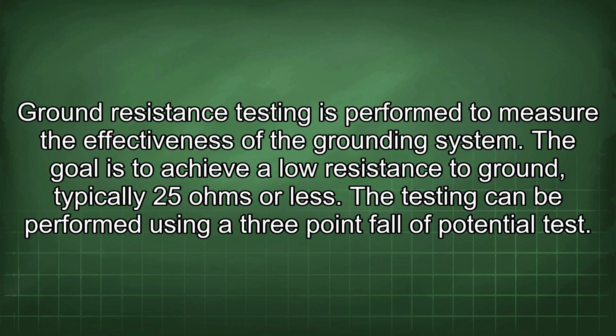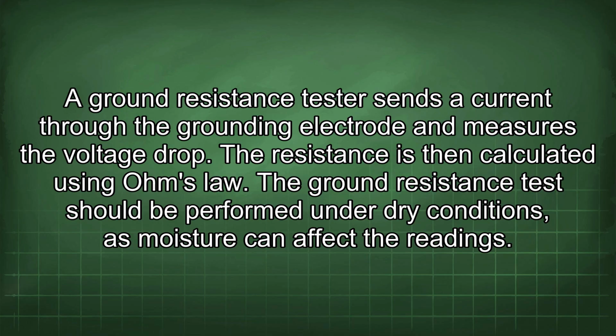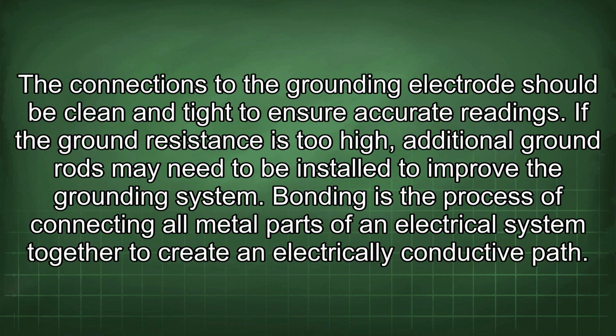The goal is to achieve a low resistance to ground, typically 25 ohms or less. The testing can be performed using a 3-point fall of potential test. A ground resistance tester sends a current through the grounding electrode and measures the voltage drop. The resistance is then calculated using Ohm's law. The ground resistance test should be performed under dry conditions as moisture can affect the readings. The connections to the grounding electrode should be clean and tight to ensure accurate readings. If the ground resistance is too high, additional ground rods may need to be installed to improve the grounding system.